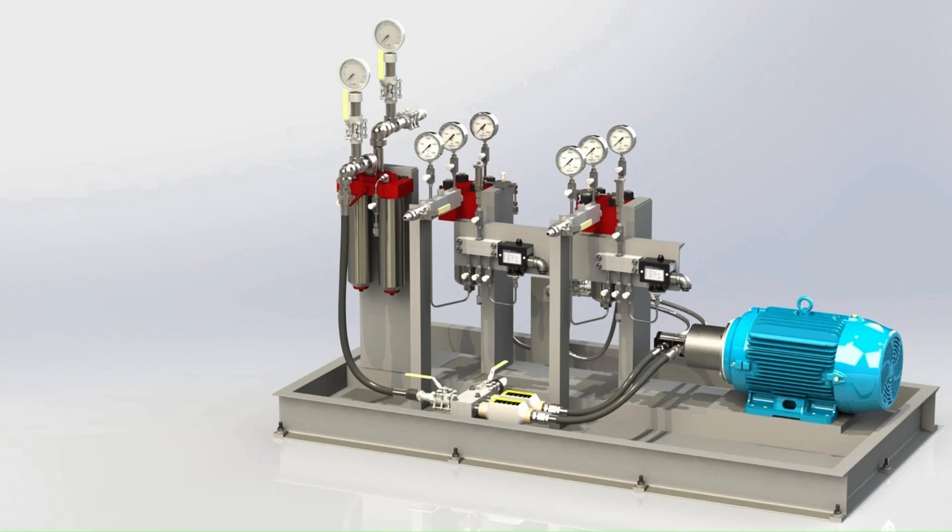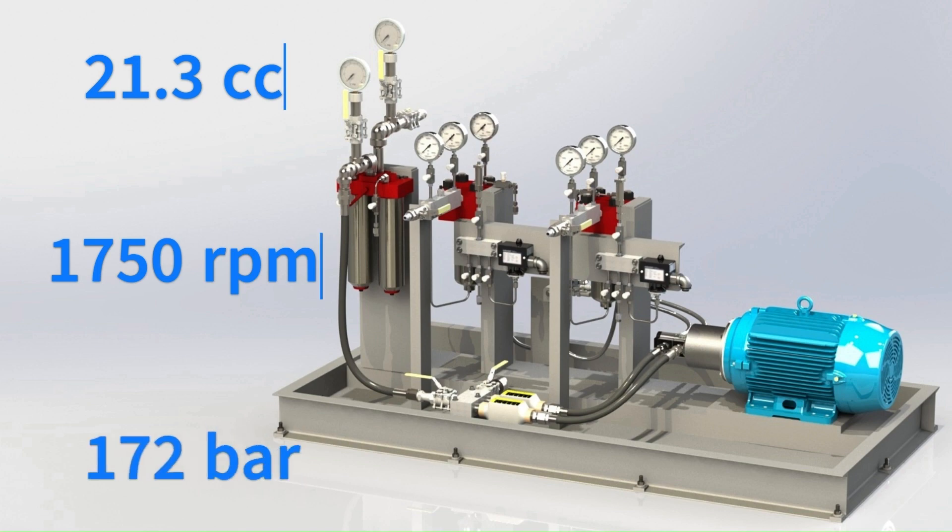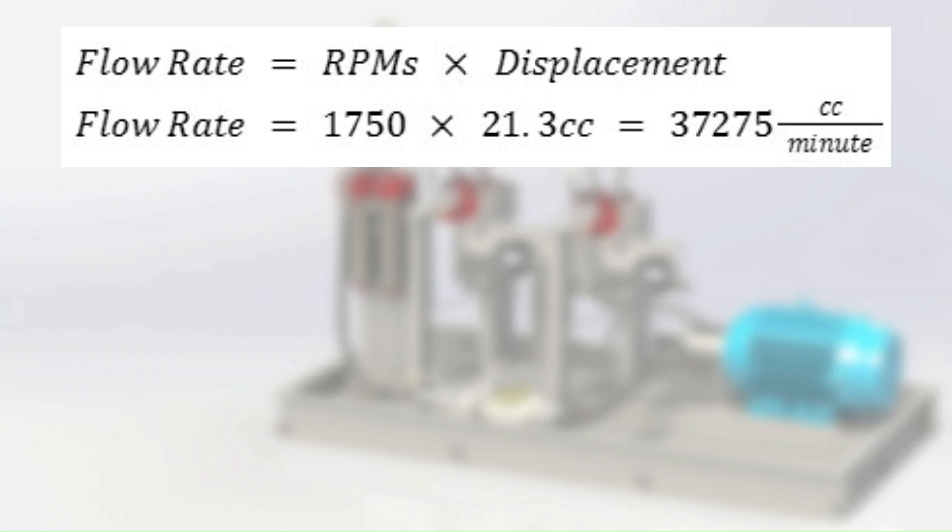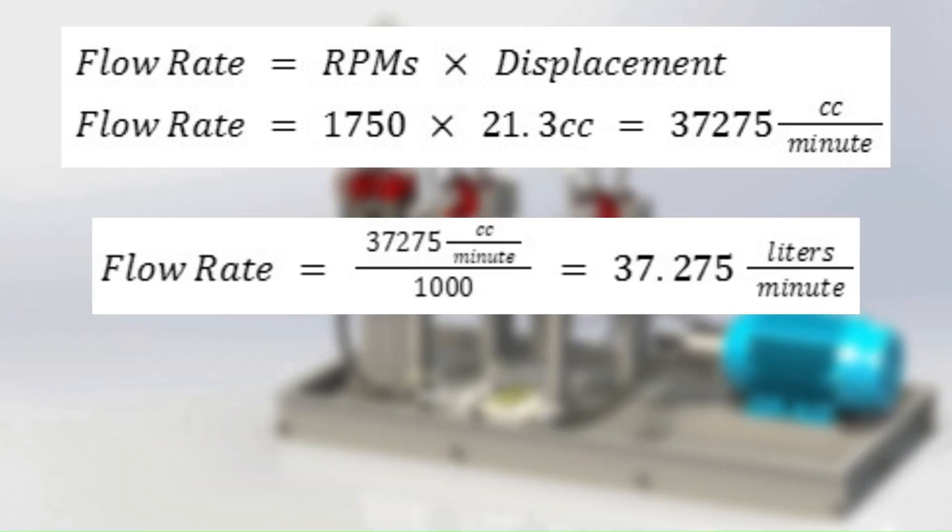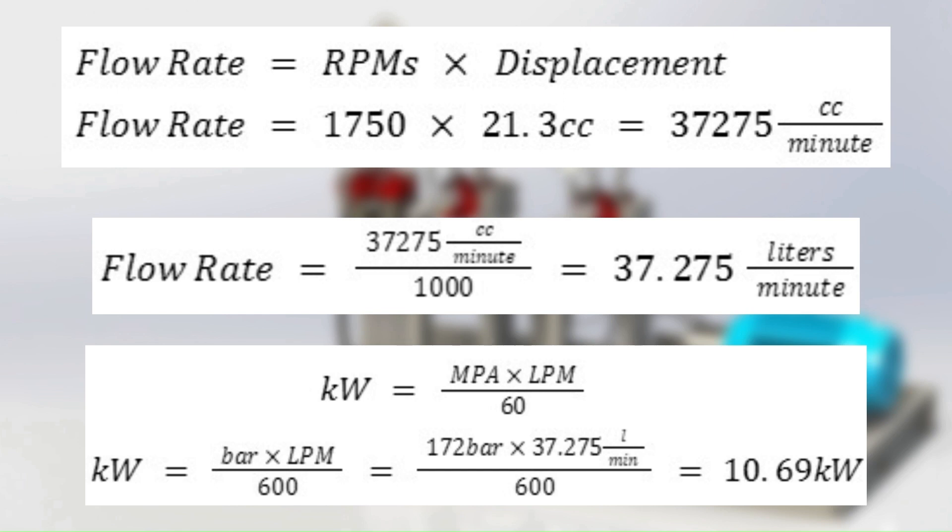If your pump displacement is measured in cubic centimeters, you can either convert it to cubic inches or stick to SI units. Doing this same example in SI units, we assume a pump displacement of 21.3 CC. Again, the motor RPMs will be 1750 and our system pressure will be 172 bar. We first find the volume per minute and then we convert to liters per minute. Running this through our kilowatt equation gives us 10.69 kilowatts.